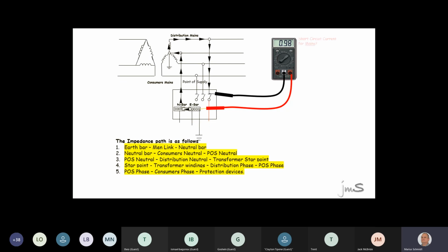230. How many amps are you going to get? Right, 234 amps. So guys, if you would have taken the voltage divided by the amps at this switchboard, 234 amps is going to flow here. That is your PSC, your short circuit current.